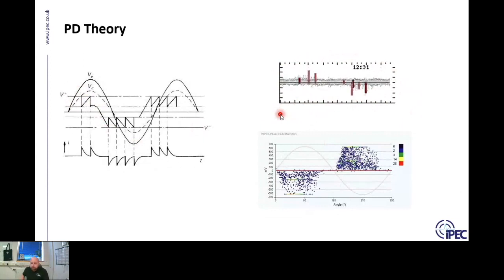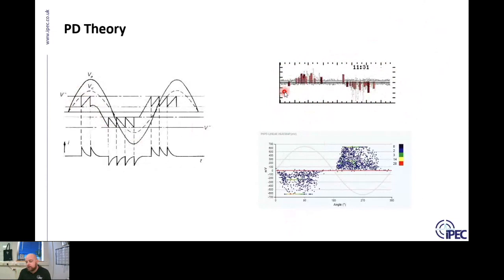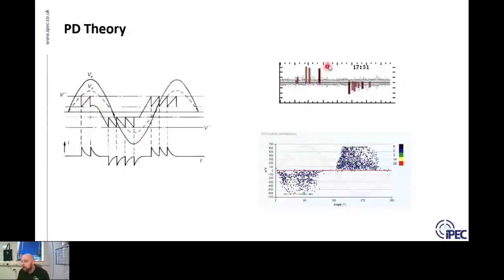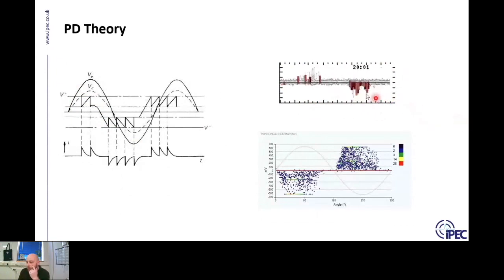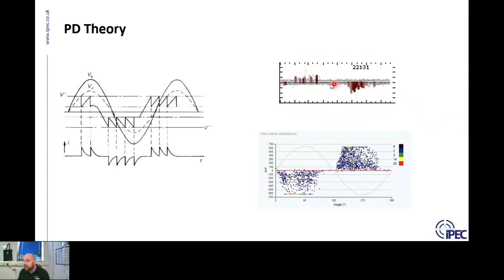This animated GIF from our monitoring system shows each bar as a highlighted point of potential partial discharge against background noise. As energy in the power cycle increases, PD occurs; crossing zero and increasing on the negative side, PD occurs again. We get these typical PRPD phase resolved partial discharge patterns with 180-degree shifts in PD activity across the power cycle.